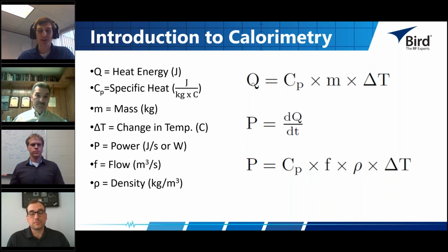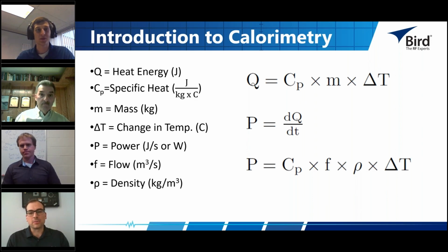So Jeff, to your point, I know there's a lot of complex system dynamics at play here. Even just looking at the equations, you can see we're really focused on a power level. Now, is the 0.5% accuracy okay across the dynamic range of the 0.5% sensors? Jacob could probably answer that better than I can, but we usually quote 0.5% at the calibration frequency and power level, and then there is some wiggle room outside of that, but I'll let Jacob answer that one more.